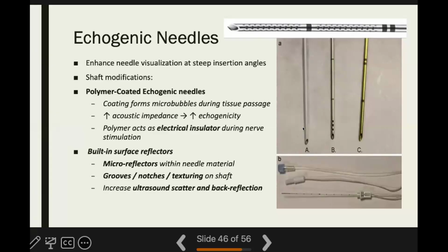So we have four types of needles here. The first one here in A is the polymer coated echogenic needle. These needles basically form a sheet of microbubbles along their surface when they're passing through the tissue. So they will increase the acoustic impedance and increase the echogenicity. Along with that, this polymer gives us another advantage, that it acts as an electrical insulator. The second is going to be certain grooves that have been made into the tip of the needle.